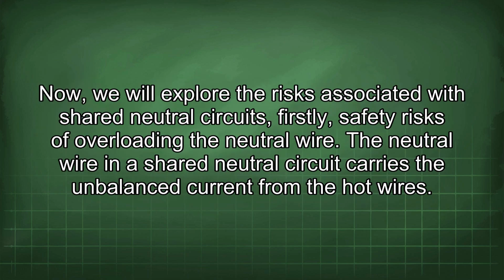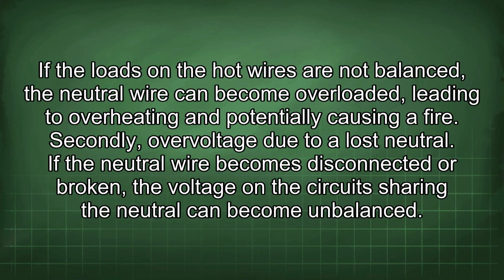Now, we will explore the risks associated with shared neutral circuits. Firstly, safety risks of overloading the neutral wire. The neutral wire in a shared neutral circuit carries the unbalanced current from the hot wires. If the loads on the hot wires are not balanced, the neutral wire can become overloaded, leading to overheating and potentially causing a fire.